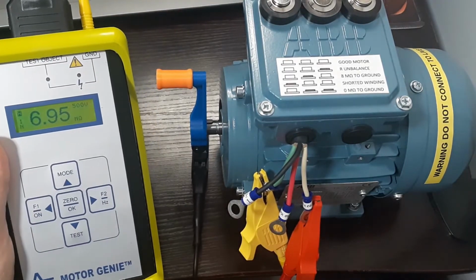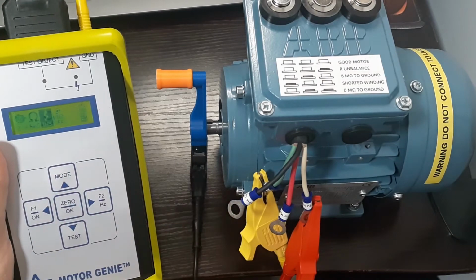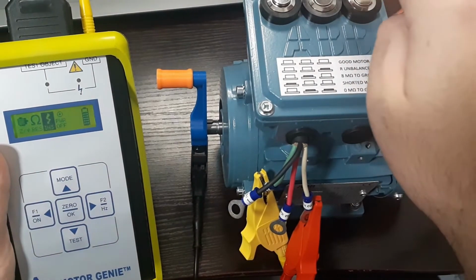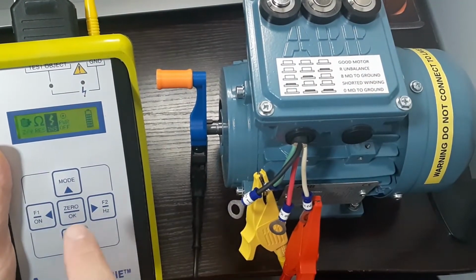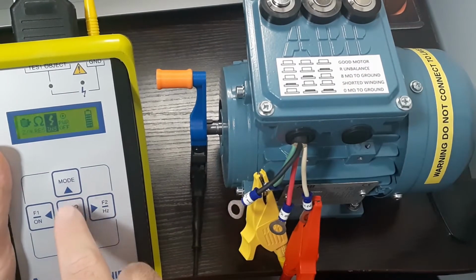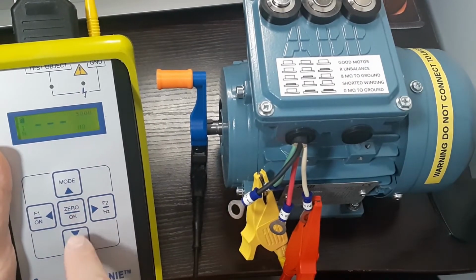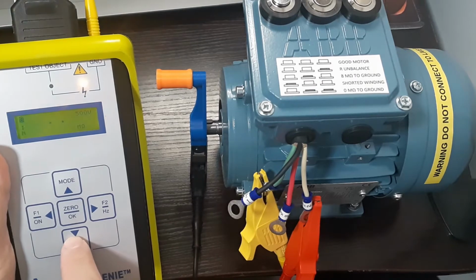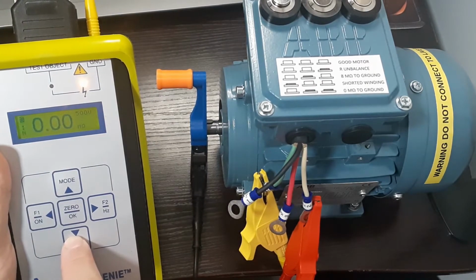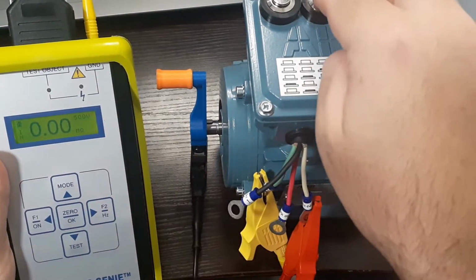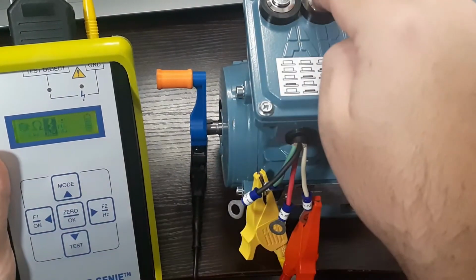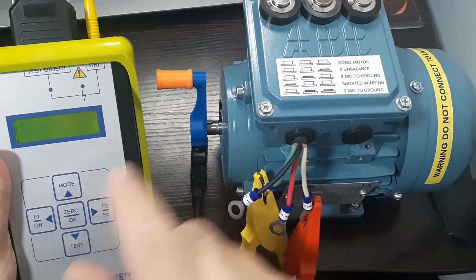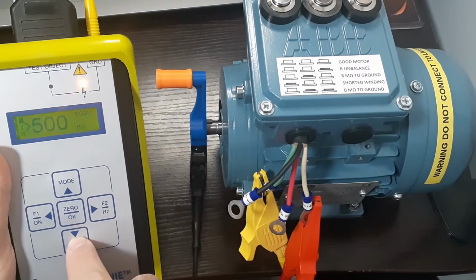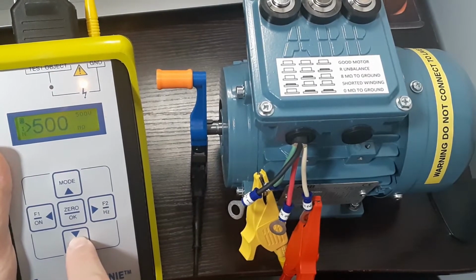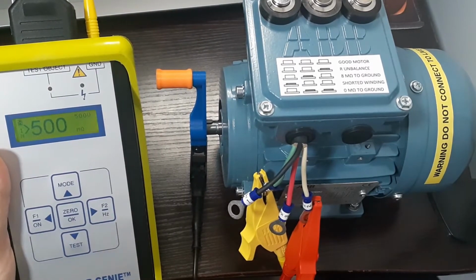So, not passing. We'll go back to the main menu. We can go 0 mega ohm to ground. This is a test motor from ALLTEST, so that's been modified to put these faults in. And there we go, we've got 0. Whereas, if this is a perfectly working motor, like now it's selected to be, we have over 500. Nice and easy. That's it, doing the mega ohm testing.